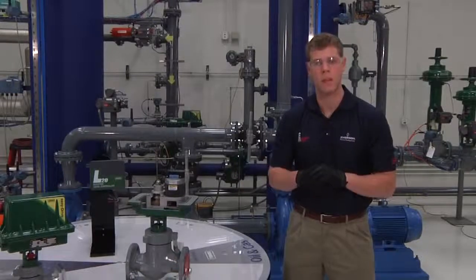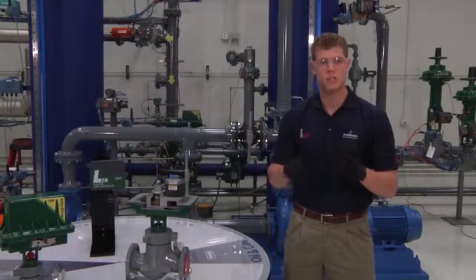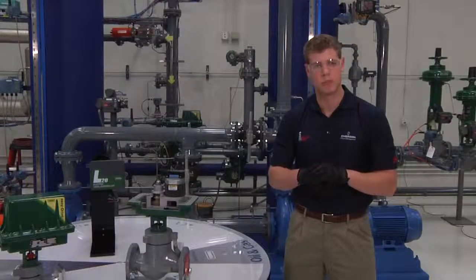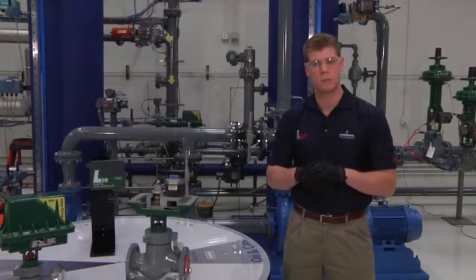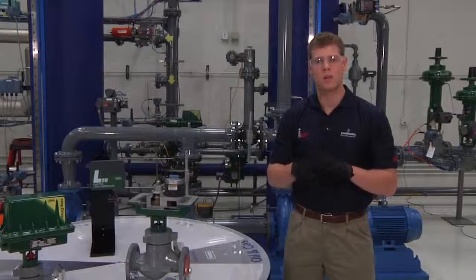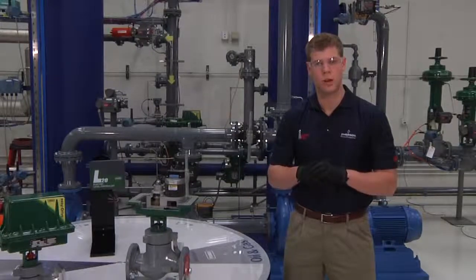During initial setup, ensure a stable DC power source is available and sufficiently surge protected for the application. A 4 amp minimum power supply is required. Use of a 36 volt transient voltage suppressor is also highly recommended.